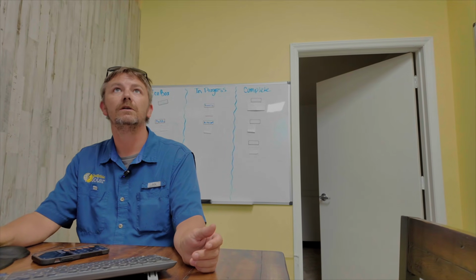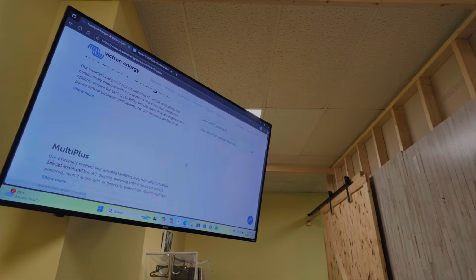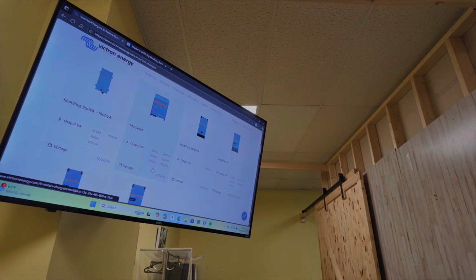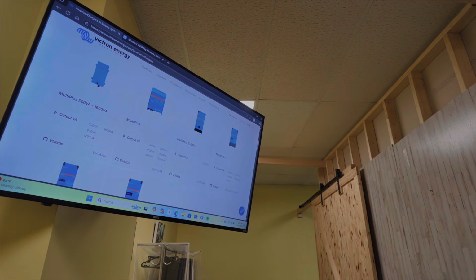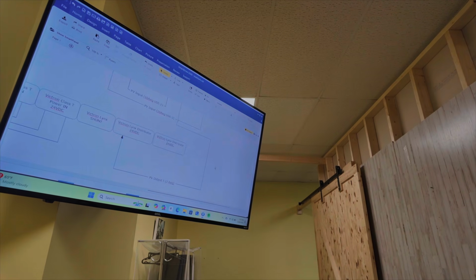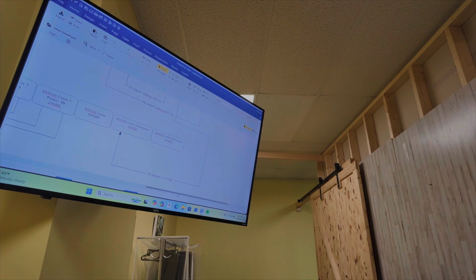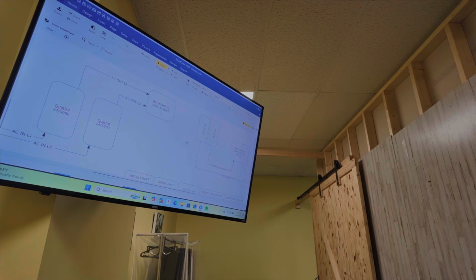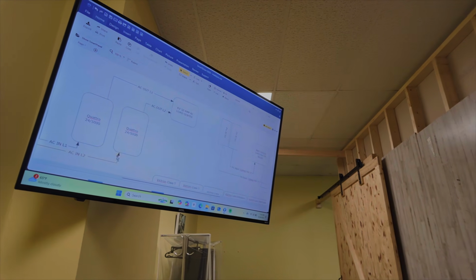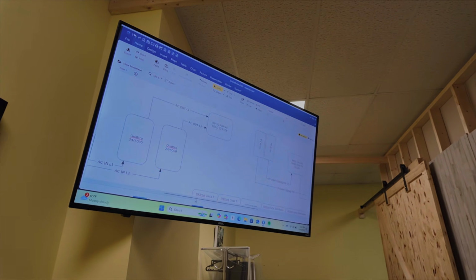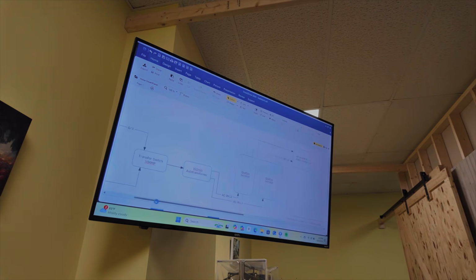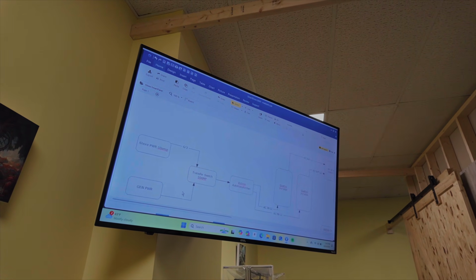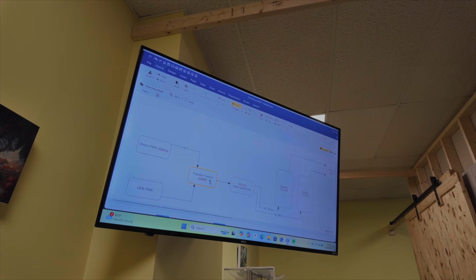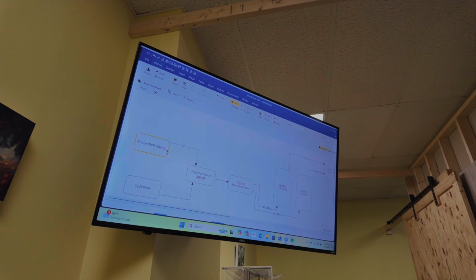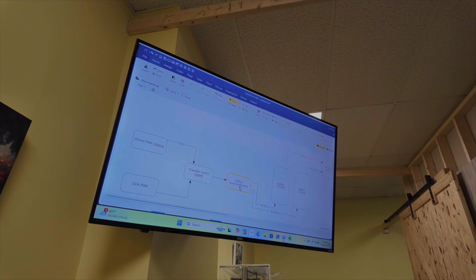You don't necessarily even need the quattros, because we're going to do the switching before the inverter. So we don't need the quattro's three-way switch, because the quattro itself has an input for shore and an input for generator, and it does the transfer on its own. But because we want to run things through an auto transformer, we'll need to do that switch after shore and gen. Then the switch will go to the auto transformer.